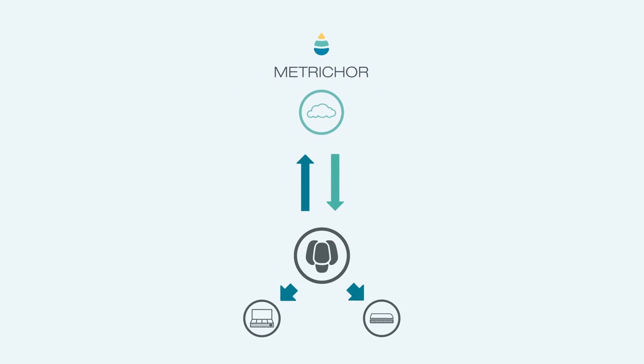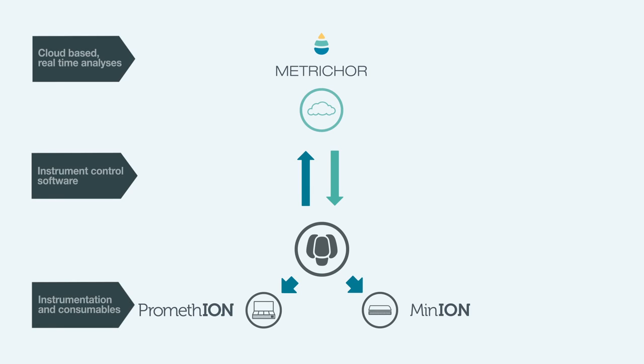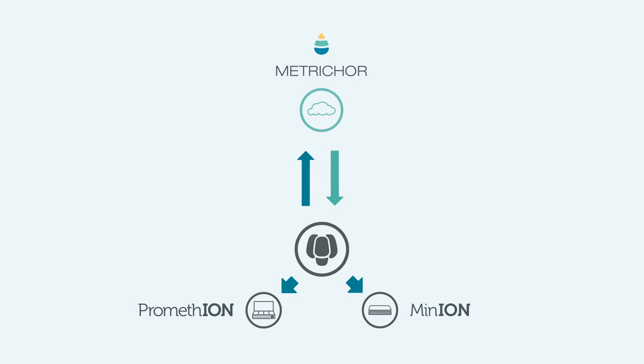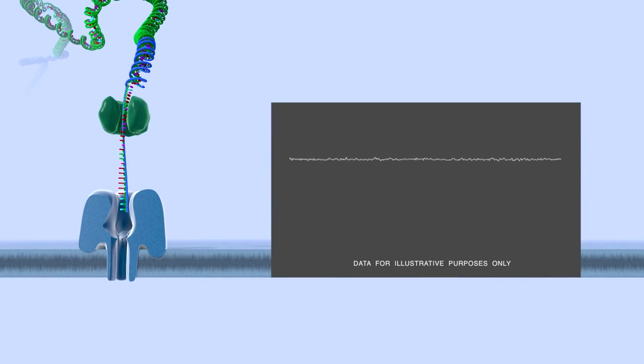This allows the user to continue an experiment until sufficient data has been produced to determine the answer to the biological question, for example, the presence of a specific mutation. Once that event has been detected with the required level of confidence, the experiment is completed and the instrument can move on to another experiment or sample.